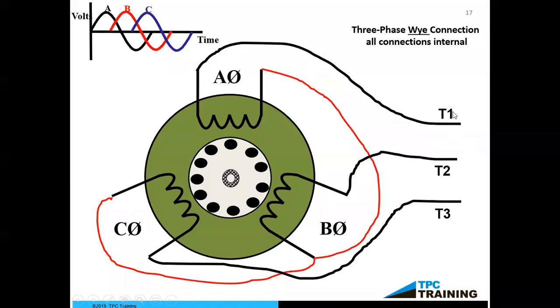So if I put that meter right between T1 and T2, I can identify immediately if A and B windings are good. What should I get when I do that for a reading? Well, I should get on a regular three-phase induction motor, a number between 10 and 30 is real good. Now, I have seen on some high-efficiency motors that reading be up near 150 ohms. It all depends how the motor was wound and how the manufacturer developed their windings.